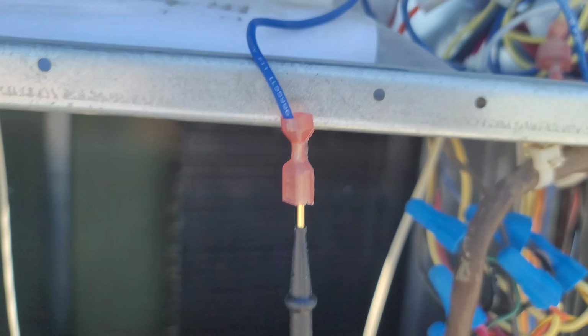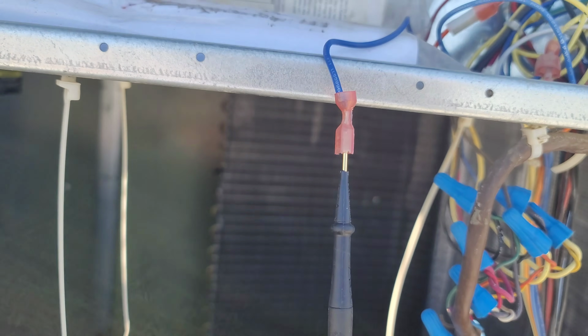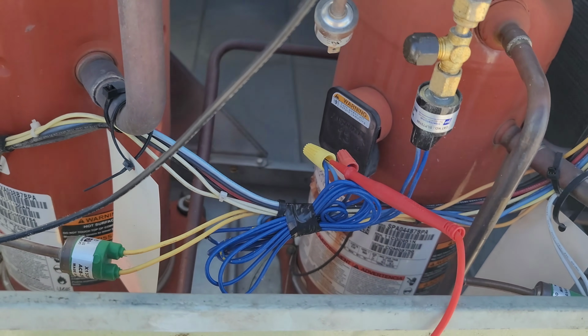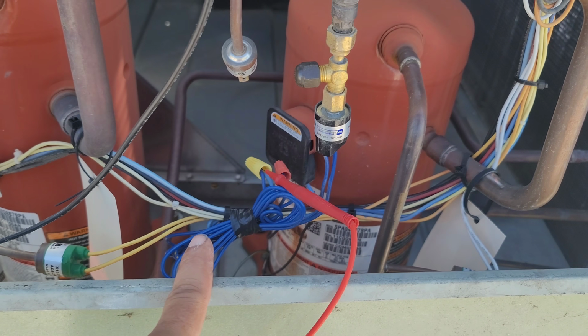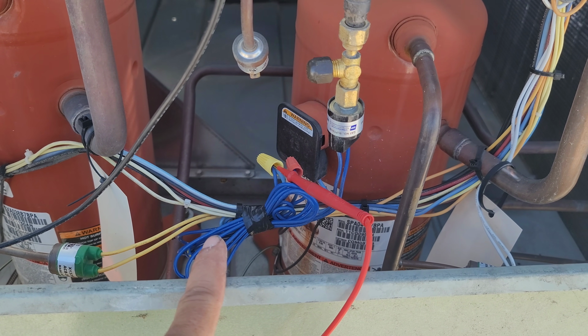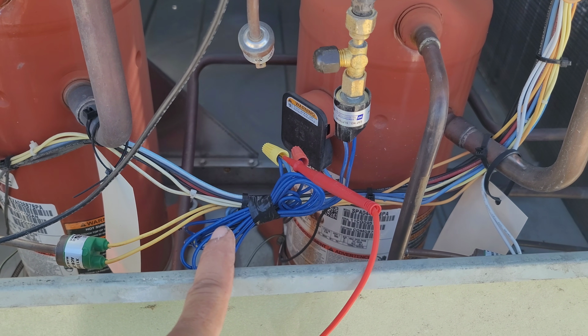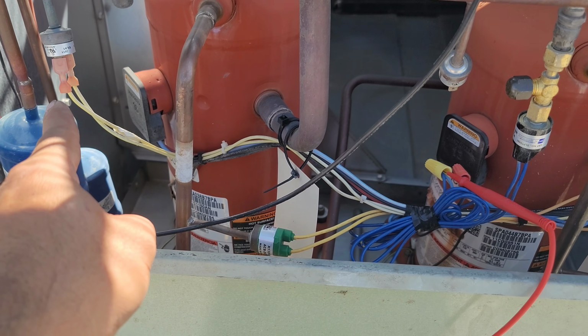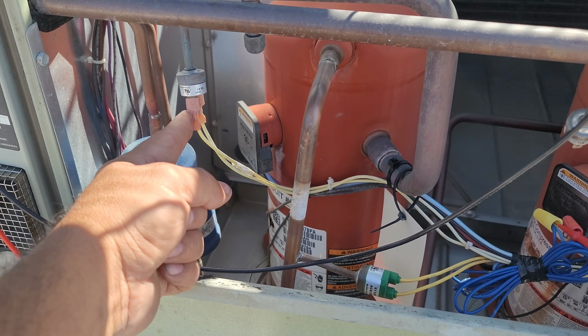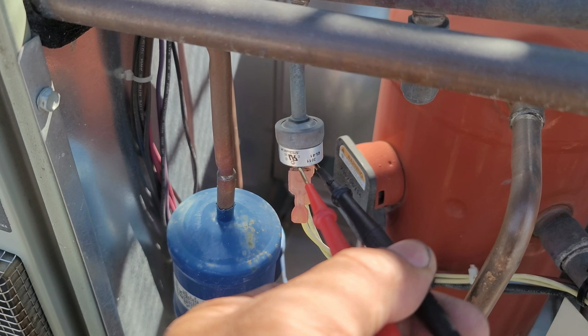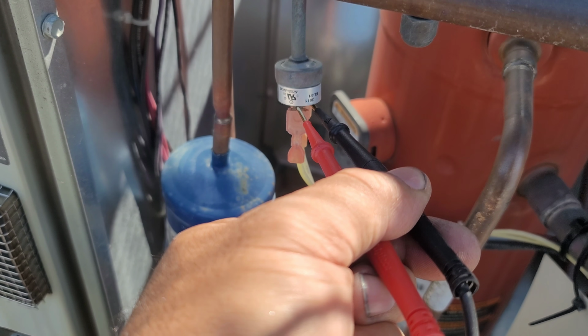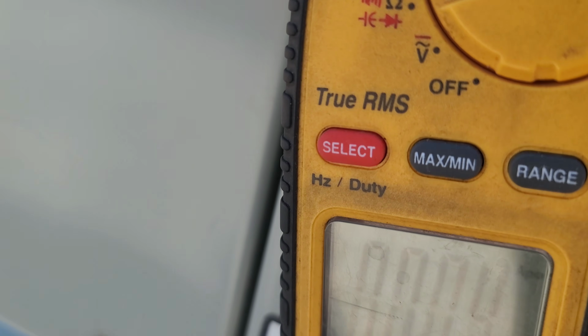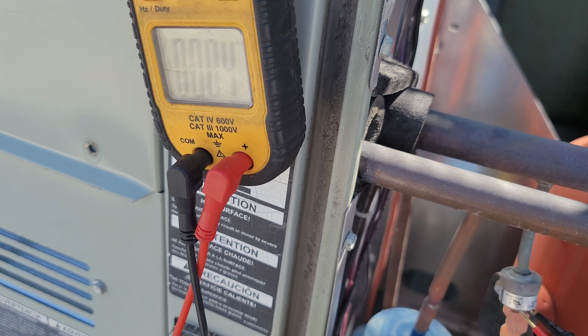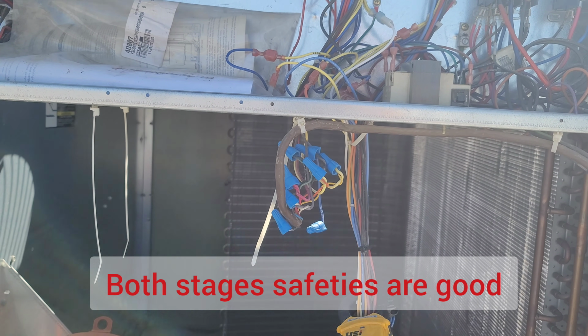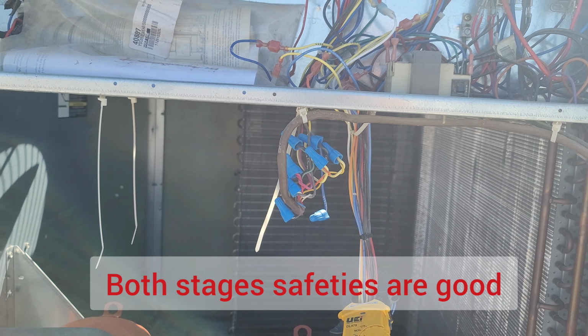Okay, as you can hear, I have inserted my terminal in blue, and the second one is from this here. So the circuit 1, all the safeties are closed, so all the safeties are okay. Same thing, we're going to check the second stage. The second stage, this one is easier to check. Second stage, low pressure switch has a beep, that means it's closed. Okay, so the first stage safeties and the second stage safeties all are closed.